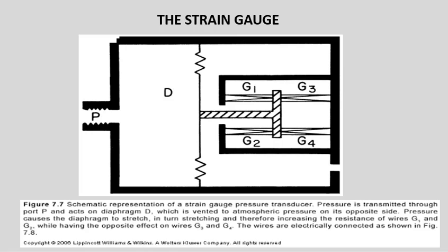I think a 5-year-old child can reproduce this. It's the strain gauge. Let's have a look at the strain gauge. The strain gauge is simply a representation of the design of a transducer, and a transducer is what we use to measure blood pressure. It's about the size of a thumb drive, and it's connected to the patient via a little pressure line, simply plastic tubing, to the inside of the patient's artery, so that when you have a heartbeat, systole will deflect this little membrane.